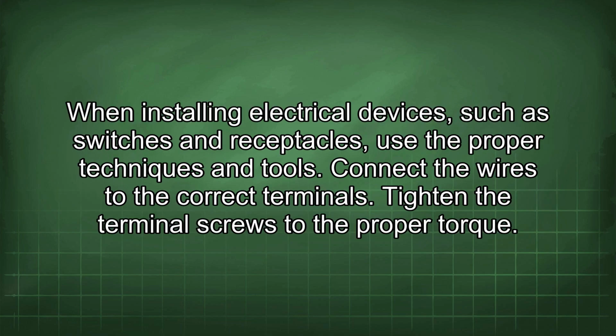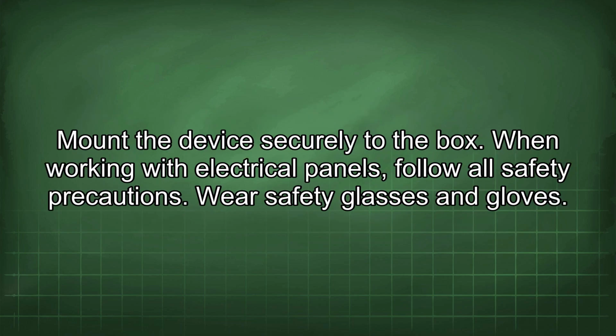When installing electrical devices, such as switches and receptacles, use the proper techniques and tools. Connect the wires to the correct terminals. Tighten the terminal screws to the proper torque. Mount the device securely to the box.